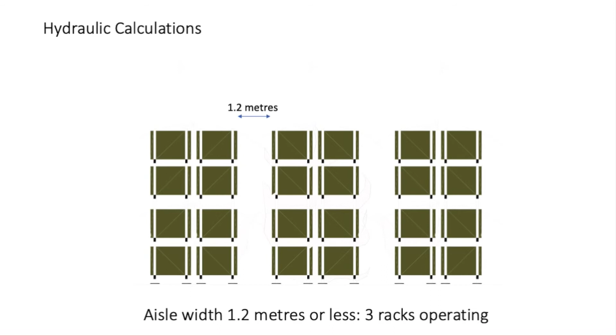When you've got aisle widths 1.2 to 2.4, what we're basically saying is that we're going to protect 2 racks in operation. So that would be 3 heads and 3 levels over 2 racks, which would be 18 heads in operation. And then when you're less than 1.2, we're protecting 3 racks in operation at 3 levels, so it would be 27. Okay, 27 heads in operation.